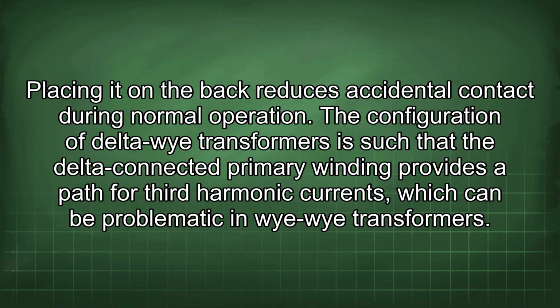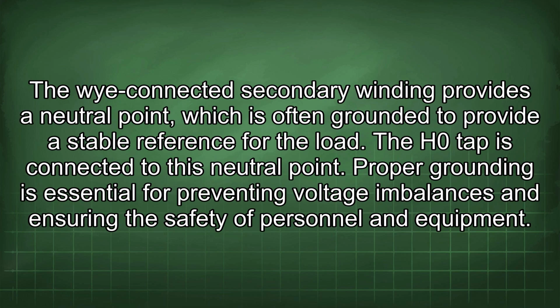The configuration of delta-wye transformers is such that the delta-connected primary winding provides a path for third harmonic currents, which can be problematic in Y-Y transformers. The Y-connected secondary winding provides a neutral point, which is often grounded to provide a stable reference for the load. The H0 tap is connected to this neutral point. Proper grounding is essential for preventing voltage imbalances and ensuring the safety of personnel and equipment.